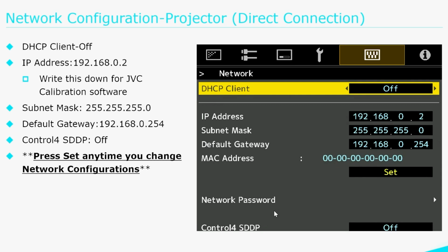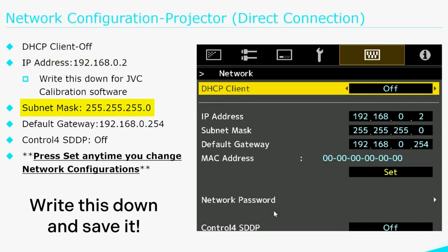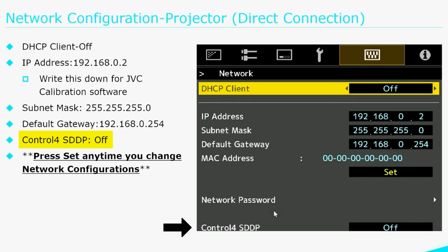Go into the network configuration and turn your DHCP client off. Select your IP address as 192.168.0.2 - write this down, you'll need it for the calibration software. Subnet mask is 255.255.255.0, and your default gateway is 192.168.0.254. Control 4 SDDP is off.